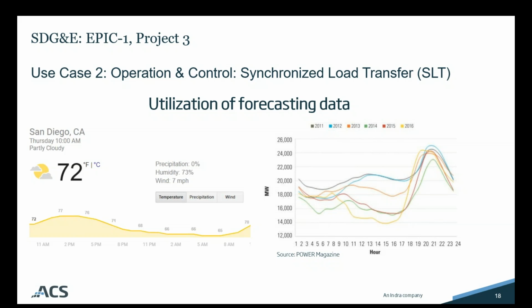So what we're doing is using rolling forecast data to continuously run future load flow analysis. And if after running that analysis, any violation is determined that cannot be mitigated from automatic resource control, as shown in use case 1, attempt to identify a new system reconfiguration, perhaps create new switching plans to maybe alleviate certain system violations, whether that's voltage or reverse power or any other violations or constraints that may hinder the distribution system.